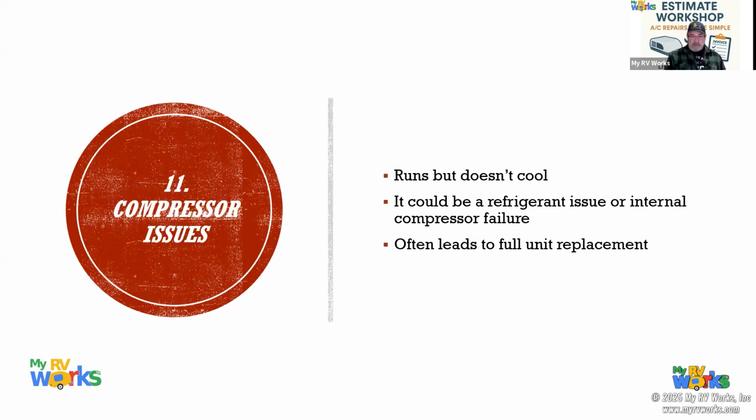And then number 11, compressor issues. Now, if your compressor is faulted, and I've got some videos out on how to check those, and on this slide here I might elaborate a little bit more. But if your compressor's got an issue, then you're looking at a full unit replacement. They're sealed. That's not field repairable.